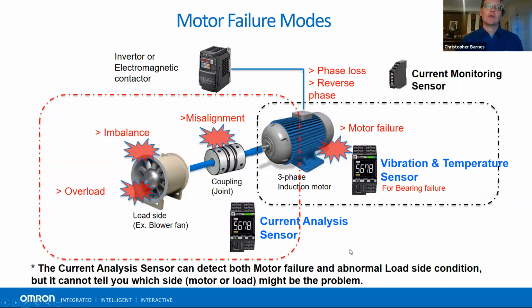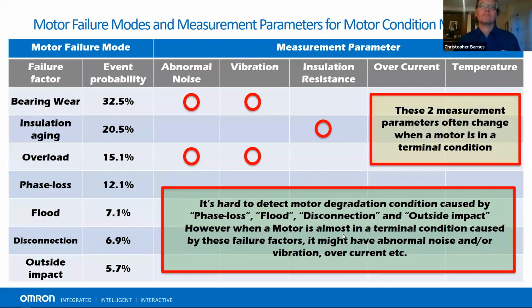And then we're also going to talk about current analysis sensors that can pick up anything from insulation resistance and leakage to other load issues. Because if there's a change in the load, the motor's going to have to work harder, and you'll see a difference in the current. The same way, if a belt breaks and there's no load, the motor's not going to work as hard, so you'll see that also show up in the current analysis. It can give you that data in a couple of different ways.